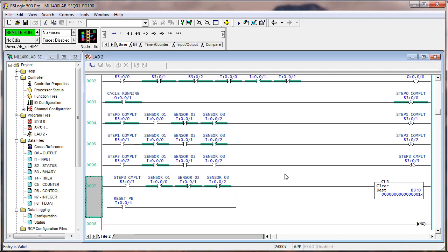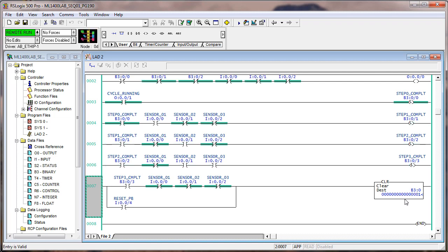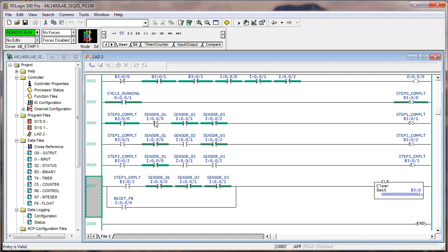So we'll go through. We have step one complete. Let's do sensor one, two, three, put the sensors back. Notice that you see the first four bits here set in B3 zero. Then we put those sensors back into the home position. And now we've reset. We've got cycle, step zero, step zero is complete. And we're ready to run another sequence. I mean, it's waiting for sensor one again.